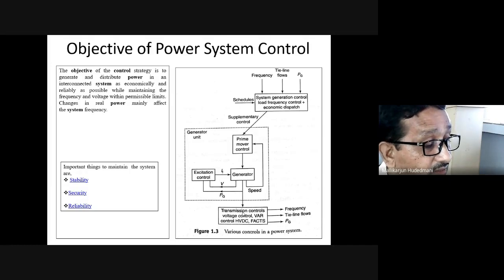Along with that, terminal voltage and megawatt power are other important parameters, which are taken into the excitation control mechanism. Again, in module number 2, we have a separate study called generator loops. We have the automatic voltage regulator loop and the automatic load frequency control loop, which are nothing but the magnified version of this block which I am trying to convey to you. So that you will see there specifically what is inside the excitation control, and how the speed feedback makes the load frequency management you will be interacting with there. Right now for us, when the generator is being driven by a prime mover, the speed feedback becomes one of the primary inputs to regulate the valve so that the RPM of the generator is managed to reach our required certain frequency.